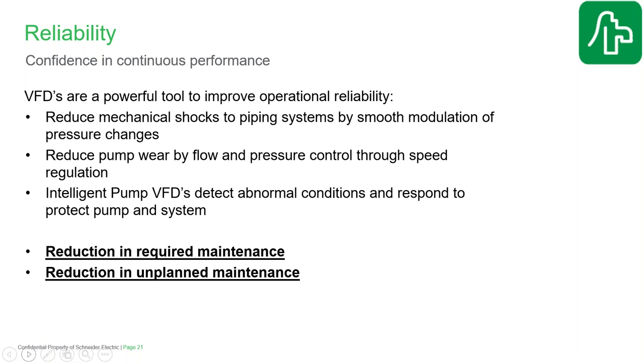First of all, by the basic principles of using a VFD, you're regulating speed and rate of pressure changes, which reduces the mechanical shocks in the piping system. That means less wear and tear, less breakdowns. But also by using that speed control instead of back pressure from a control valve, you're reducing the wear and tear on the pump. So that also helps you reduce the maintenance requirement. In addition, these intelligent drives can also look at what's going on in the drive, in the motor, in the pump, and in the system to detect abnormal conditions occurring and respond to protect the pump and the system and to ensure minimum interruption of service and notify the operators if there are any problems. So it gives you a reduction in the required maintenance and also a reduction in the unplanned maintenance, the number of breakdowns that you have.